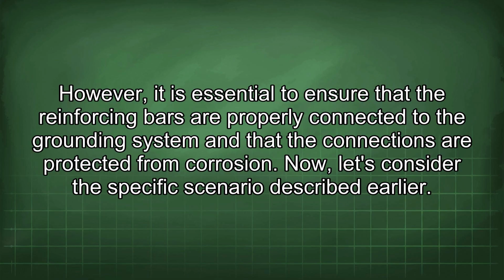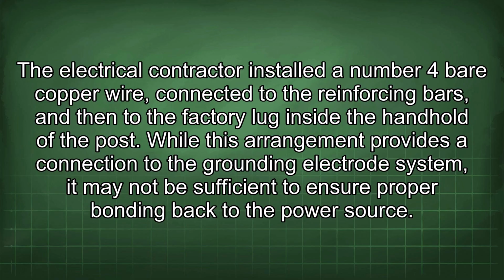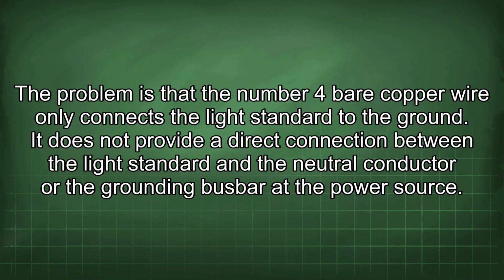Now, let's consider the specific scenario described earlier. The electrical contractor installed a number 4 bare copper wire connected to the reinforcing bars and then to the factory lug inside the handhold of the post. While this arrangement provides a connection to the grounding electrode system, it may not be sufficient to ensure proper bonding back to the power source. The problem is that the number 4 bare copper wire only connects the light standard to the ground.